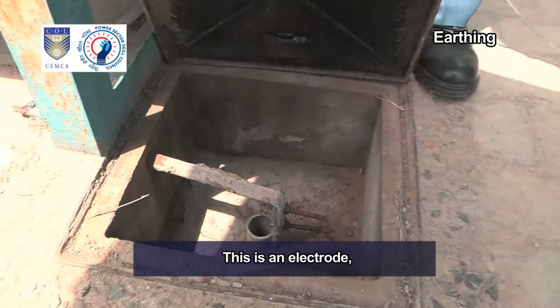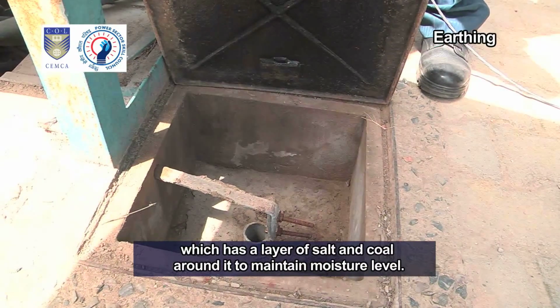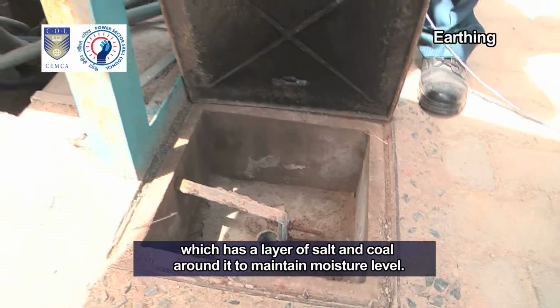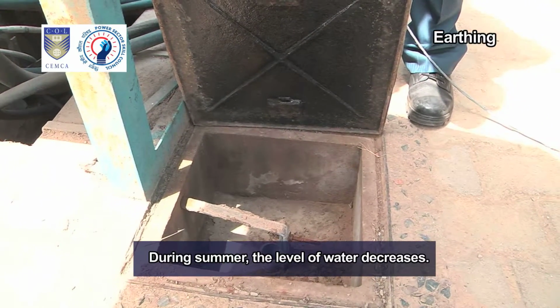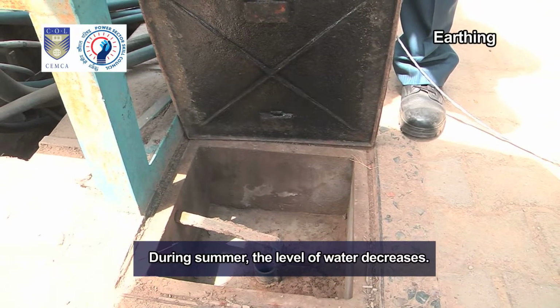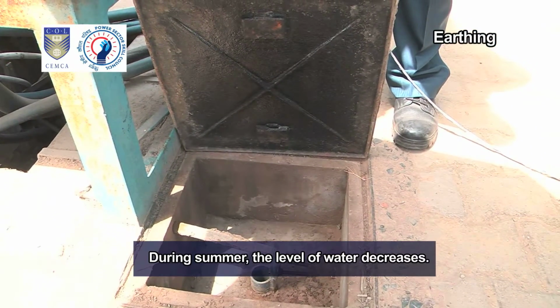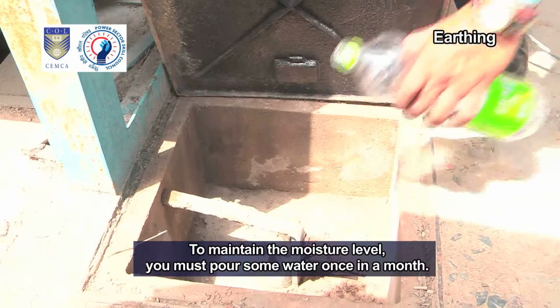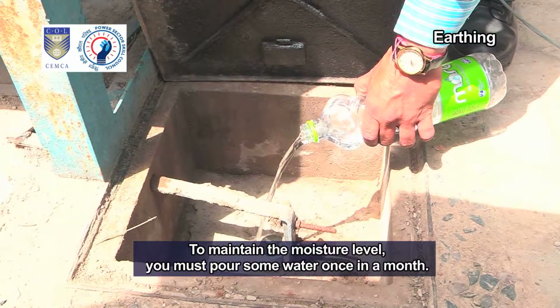This is an electrode which has a layer of salt and coal around it to maintain moisture level. During summer, the level of water decreases. To maintain the moisture level, you must pour some water once in a month.